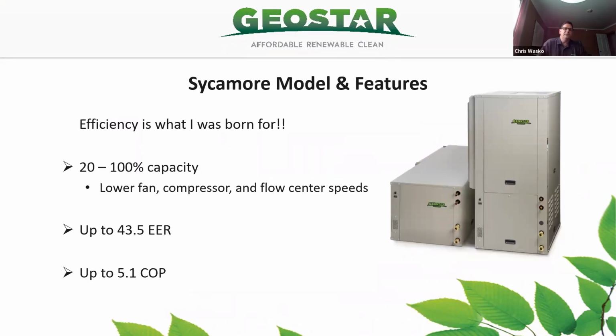Sycamore model features. So basically efficiency is what this unit was born for, right? It has 20 to 100% capacity. So anywhere up and in between, this unit has the ability to maneuver the fan speeds, the compressor, and the flow centers all in unison to be able to operate this unit at efficiency levels that are up to a 43.5 EER and a 5.1 COP. Some of the highest levels you're going to find in any HVAC there is out there, even including in any geothermal equipment you can find.